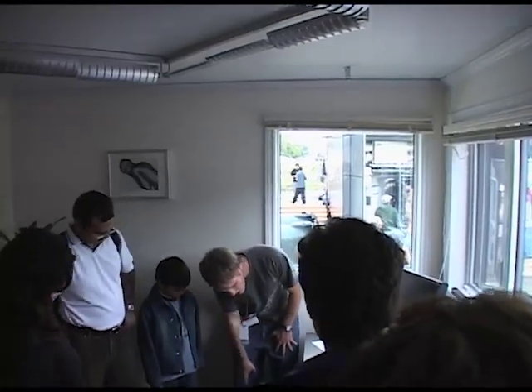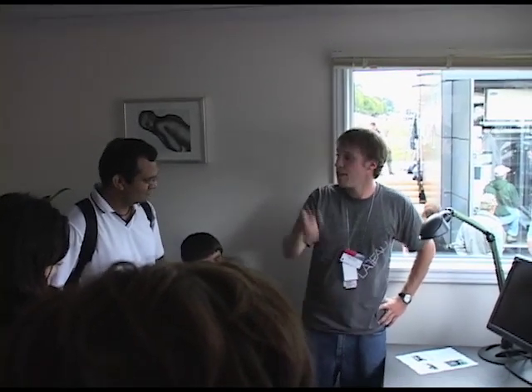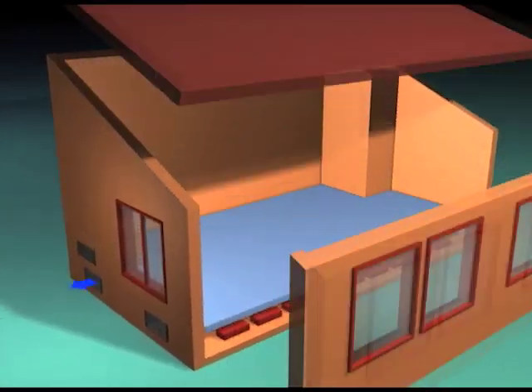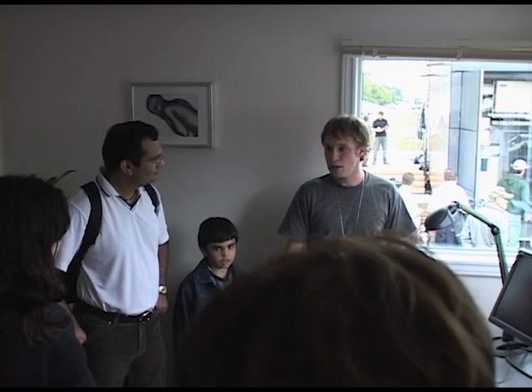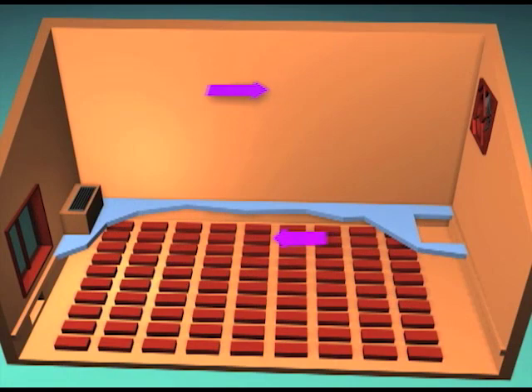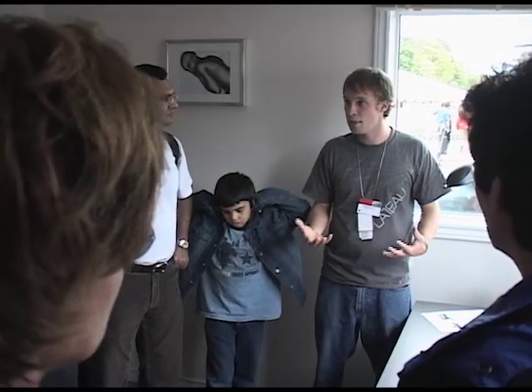The Canadian team used bricks under the floor. These bricks show how thermal mass can store both heat and coolness. In July, expecting a cool evening and night, a very large fan at the back sucks in huge volumes of air that pass underneath the floor over the bricks, which run the entire length of the house. Cooler outside air is blown over the bricks, and as the evening progresses, they cool down. By the next day, to air condition the house, the air from the space is sucked into the floor, passes over the cooler bricks, and the air temperature drops by a good 6 to 8 degrees Fahrenheit. The air blowing across the bricks cools before reaching the heat pump, which finishes the job — but now it has less cooling to do, lightening the electrical load and wear and tear.